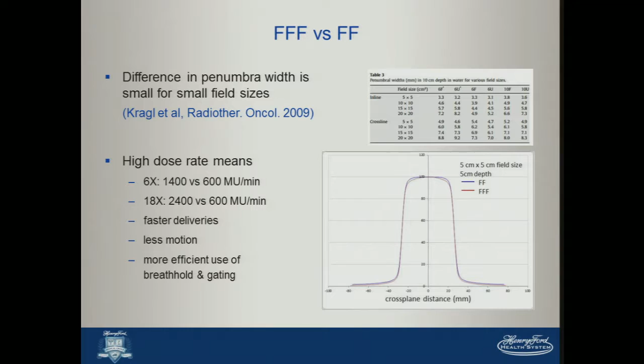Sometimes it's claimed that the penumbra there is sharper, and that's a benefit. In fact, I quoted a paper here that shows it's not particularly different. What you will get a benefit from with the flattening filter-free fields is the higher dose rates. So at least on the Varian machines, the 6X goes up to 1400 MUs per minute and the 18X to 24. So clearly a great benefit for faster deliveries and to reduce the impact of patient motion, since the patient's on the couch a lot less, or for a shorter time, and more efficient use of breath hold and gating.